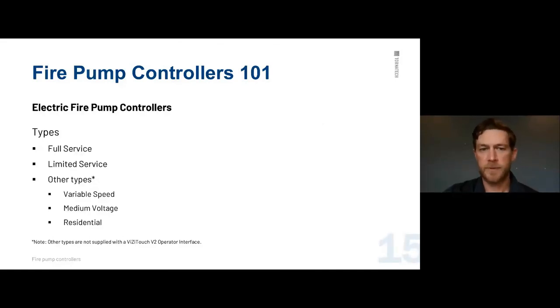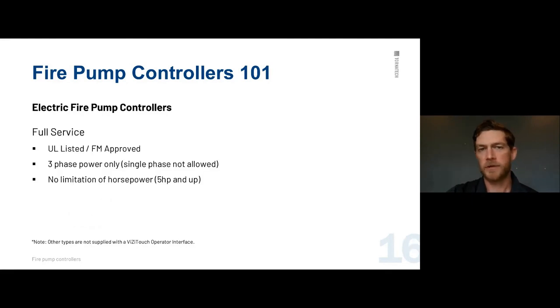Now we'll look at types of fire pump controllers. Full service controllers are all UL and FM approved — that's a requirement. They are three-phase power only; single phase is not allowed and is handled by limited service controllers. There's no limitation on horsepower for full service — five horsepower and up, with listings going to very high horsepowers. All control panel manufacturers are required to have a voltmeter and an ammeter mounted on the front door. We display this through what we call the ViziTouch, our main operator interface.